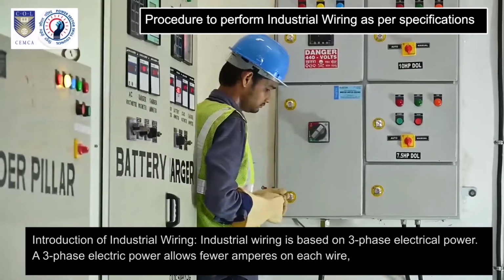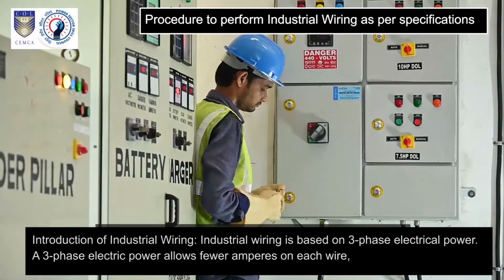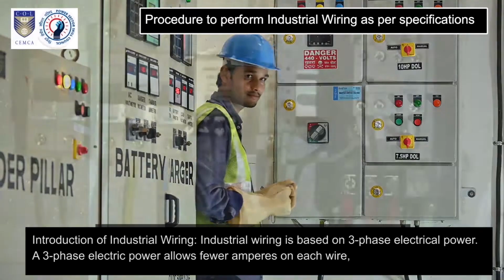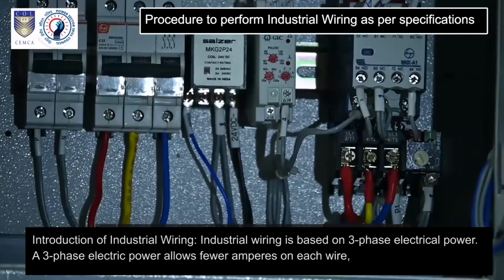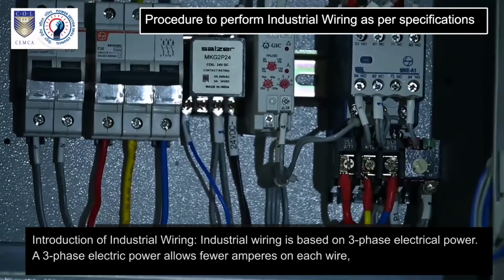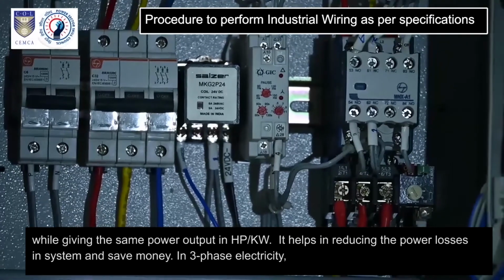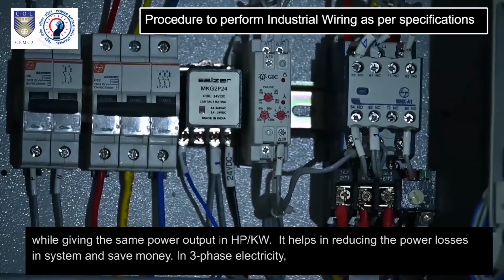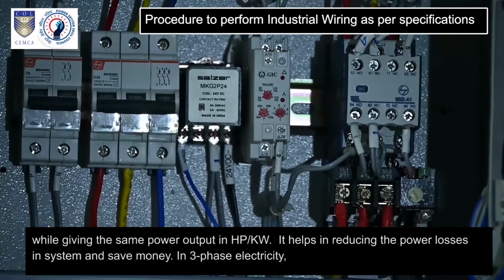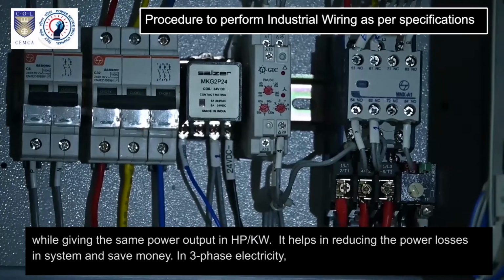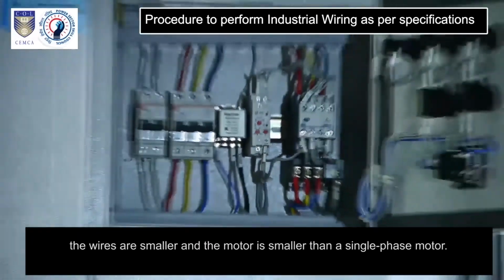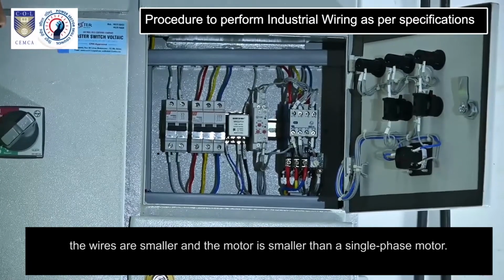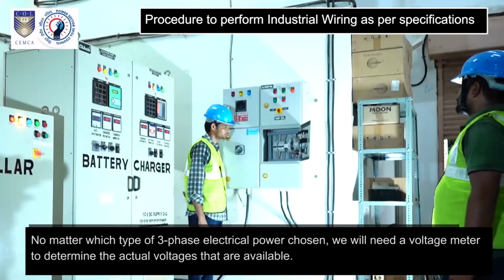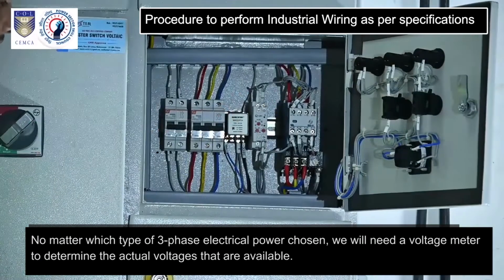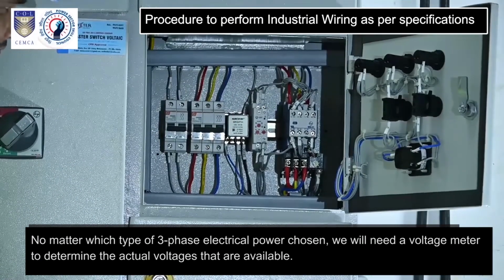Introduction of industrial wiring. Industrial wiring is based on three-phase electrical power. A three-phase electric power allows fewer amperes on each wire, while giving the same power output in HP/kilowatt. It helps in reducing the power losses in system and save money. In three-phase electricity, the wires are smaller and the motor is smaller than a single-phase motor.